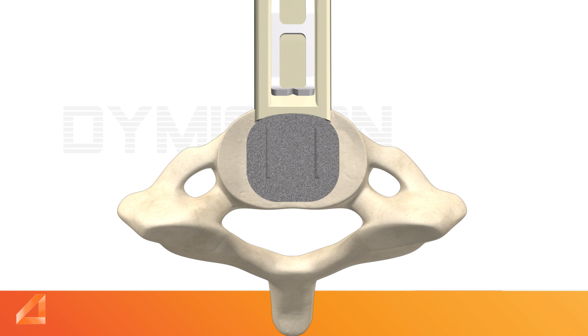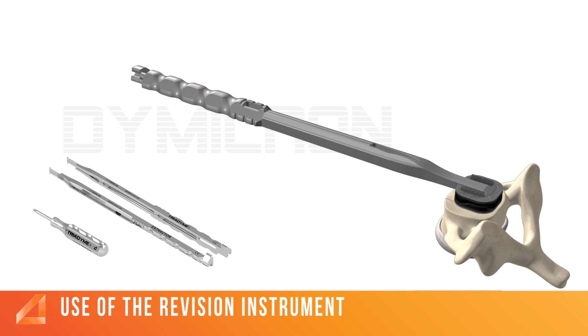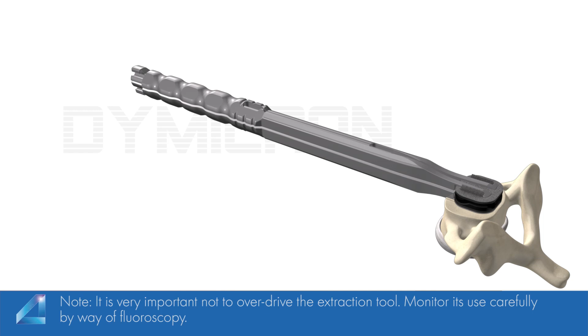In case of necessary revision or implant replacement, use the extractor as follows. Position the small osteotomes on the two halves of the extractor between the faces of the device and the superior and inferior vertebrae. Fit the two halves of the extractor together. Tighten the two small hex screws on the back of the instrument until the osteotomes hook onto the keels of the Triadyme C. Use the slap hammer to extract it.